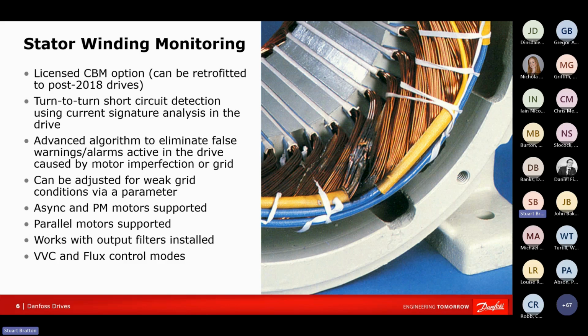Anybody that's got any knowledge at all about motor insulation breakdown will know that it's not typical for it to just catastrophically fail instantly. What tends to happen is that two adjacent coils will overheat or fuse together initially, and that leads to increased heat in that area, and eventually the rest of the windings start to fuse together, eventually ending up in some sort of catastrophic failure. So this initial fusing of two adjacent coils could be weeks or even months ahead of the final failure. And the drive is able to detect that.